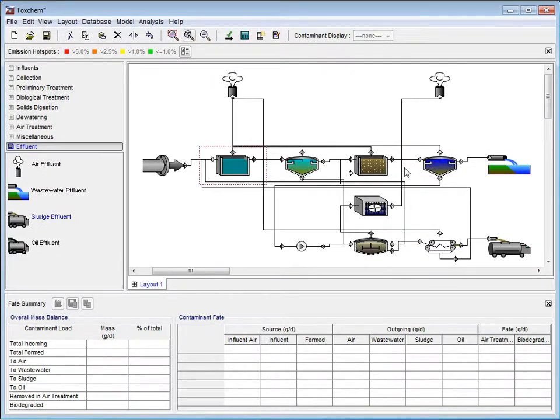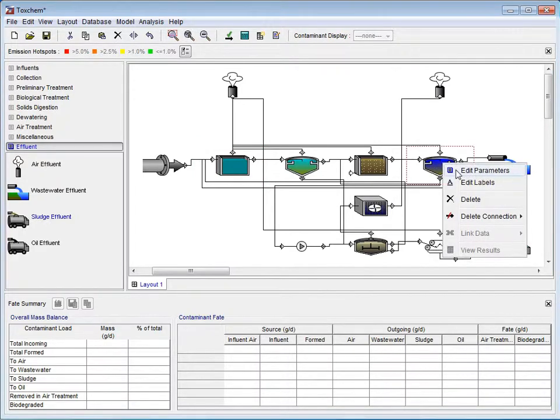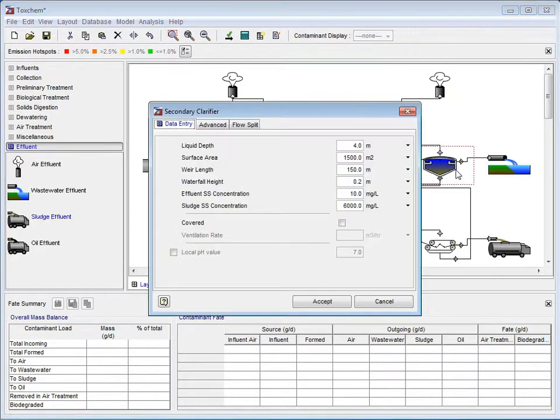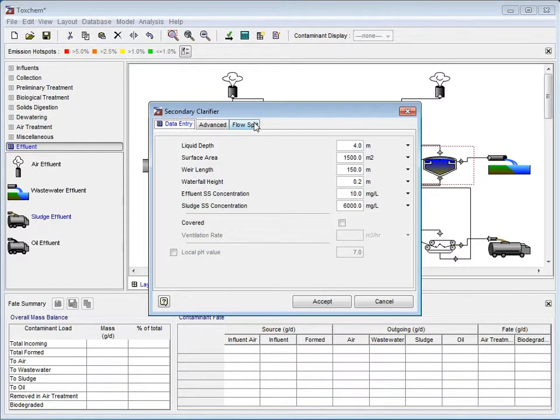Now, we will move on to the secondary clarifier. Again, right-click on the process and select Edit Parameters from the drop-down menu. In the secondary clarifier pop-up window, select Flow Split and type in 0.98 into the box beside the RAS connection. Notice here that ToxChem has automatically given the WAS stream the remaining available flow. Click Accept to go back to the Layout screen.